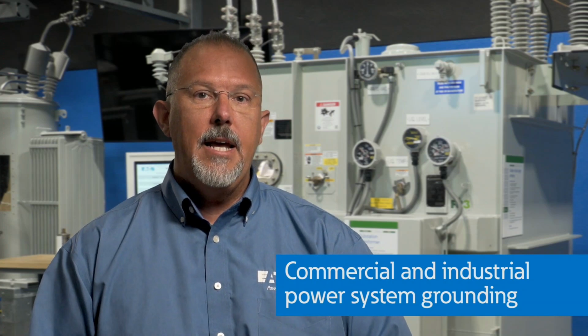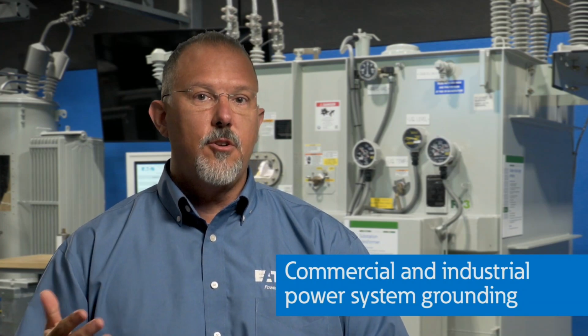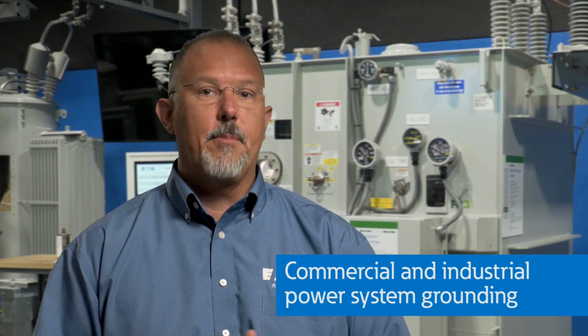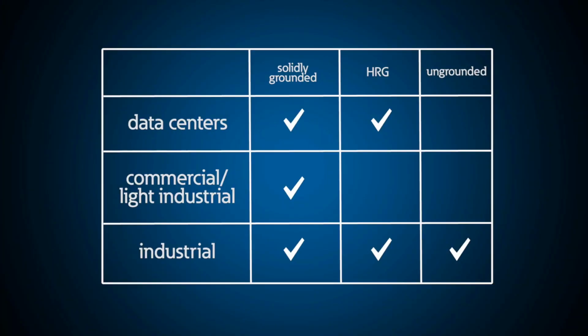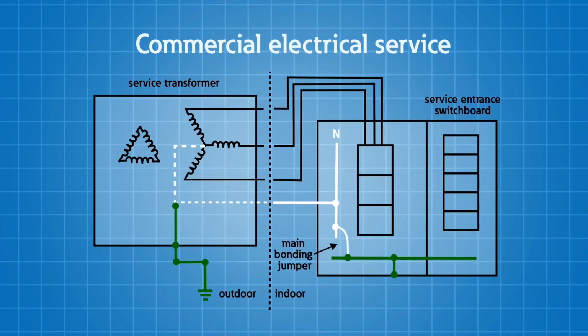So now let's look at a commercial power distribution system. As you get outside the residential world, you have more options based upon the applications. For example, data centers and other systems that demand a higher service continuity may opt to use high resistance grounded systems as opposed to solidly grounded systems. Many commercial and light industrial systems will be solidly grounded. Let's show you how a pad mounted transformer might be grounded and bonded, and how the indoor switchboard might be grounded and bonded for a solidly grounded commercial power distribution system.